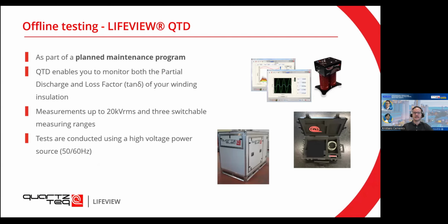QTD is essentially part of the planned maintenance program. The complete kit would perform offline PD measurements and the tan delta measurements. The tests would be made with an external power source that must be available at the site, at 50-60 hertz, and measurements up to 20,000 volts can actually be made.